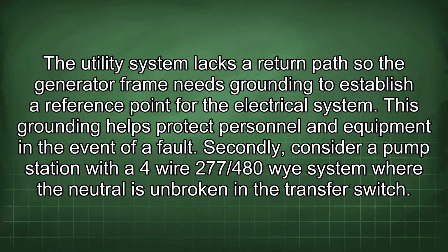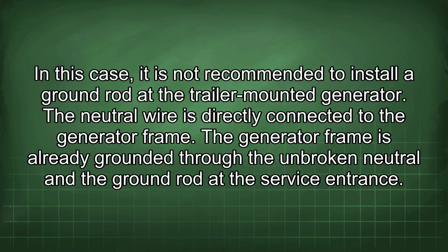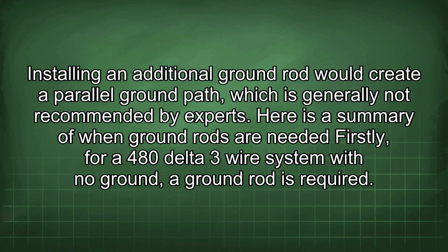Secondly, consider a pump station with a 4-wire 277/480Y system where the neutral is unbroken in the transfer switch. In this case, it is not recommended to install a ground rod at the trailer-mounted generator. The neutral wire is directly connected to the generator frame. The generator frame is already grounded through the unbroken neutral and the ground rod at the service entrance. Installing an additional ground rod would create a parallel ground path, which is generally not recommended by experts.